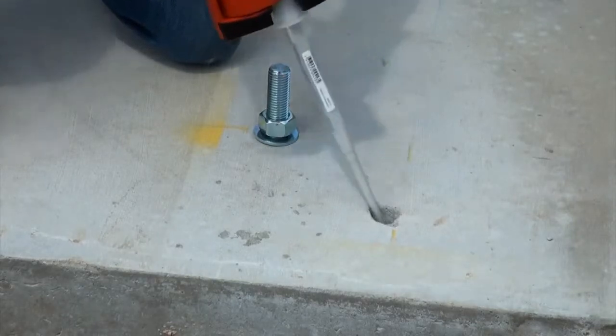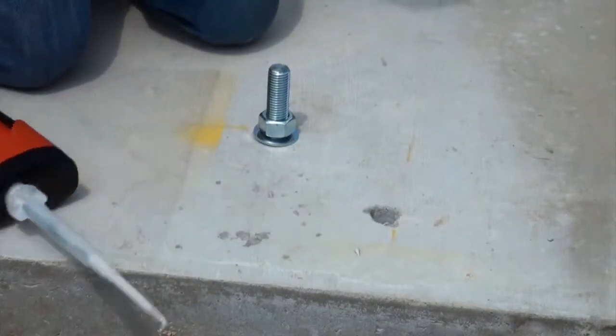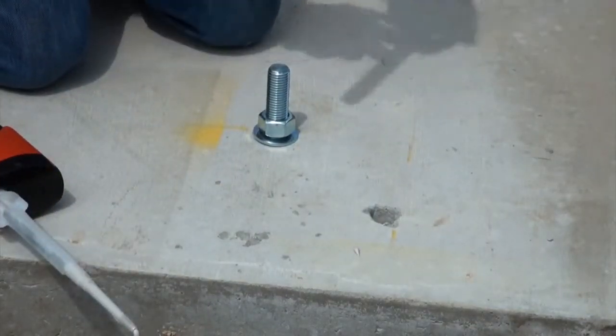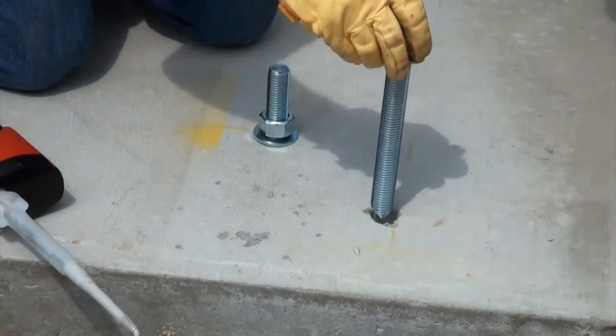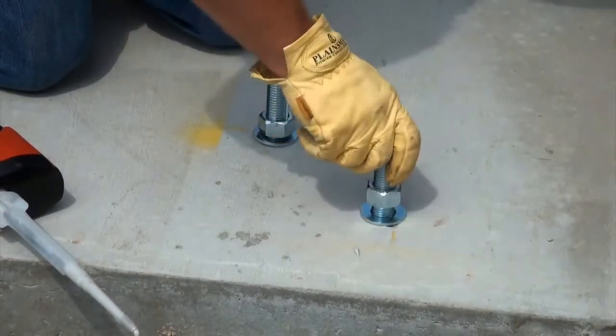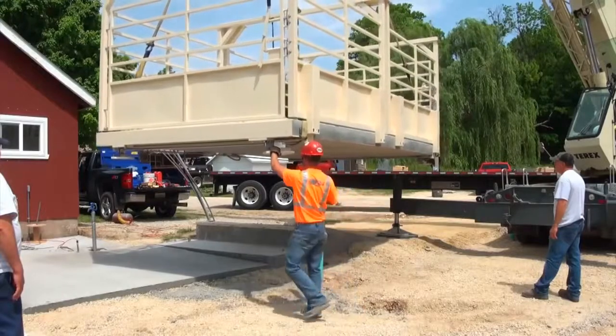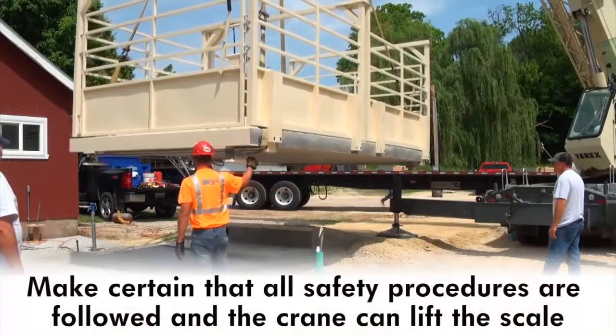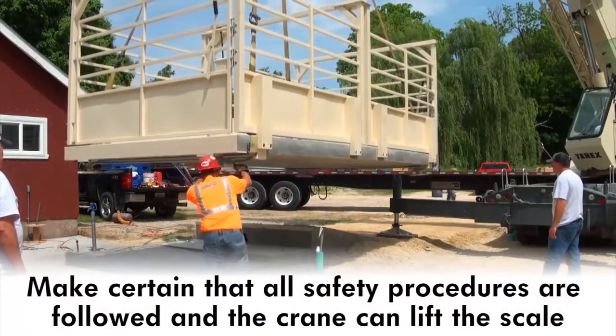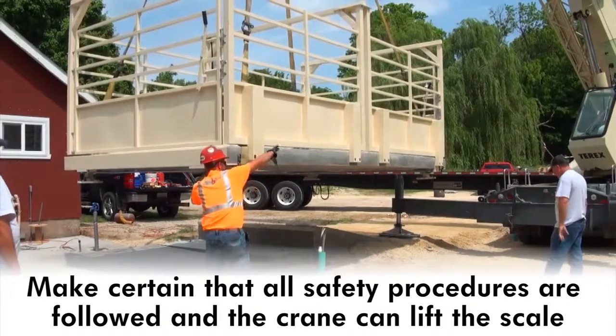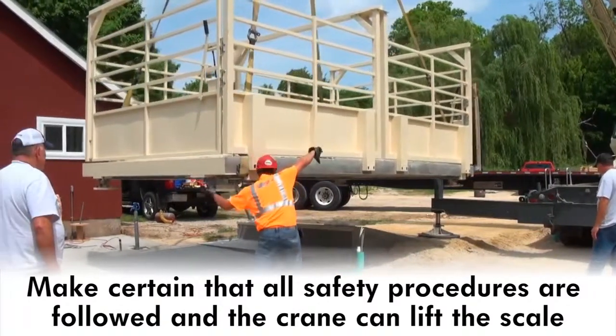Insert the anchor bolts into the drilled holes after applying a generous amount of the epoxy recommended by Cardinal Scale. Once set, the scale may be installed. Before lifting the weigh bridge, make certain that all appropriate safety procedures are closely followed and that the crane has sufficient capacity to lift the scale.